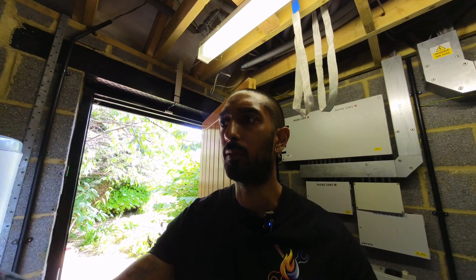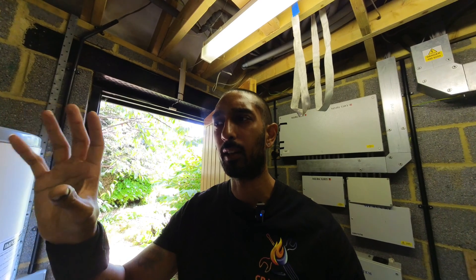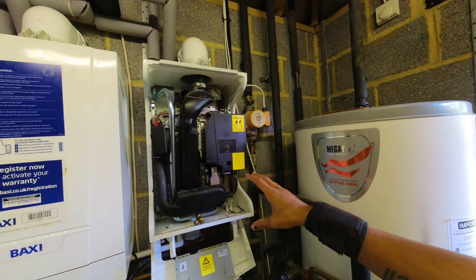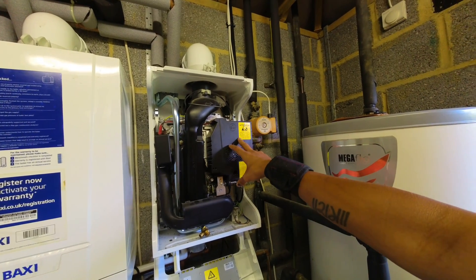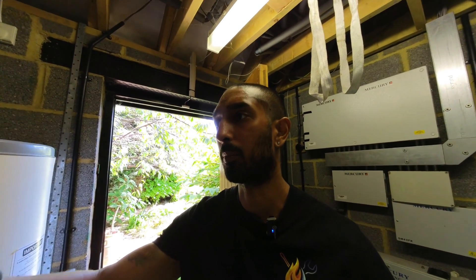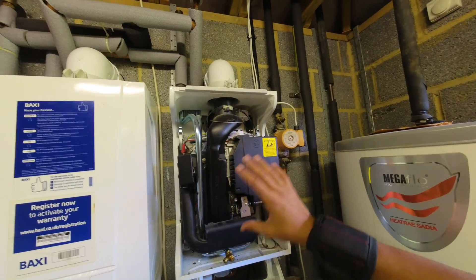When I was working in social housing I found that a lot of these used to fail. I was told by Baxi it was something to do with being fitted on S-plan systems — the voltages coming back from the three-port valve would fry the PCBs. You'd get four red flashes indicating a fan fault, meaning you had to change the whole combustion control unit. The downside is that if the gas valve, fan, or PCB fails, you have to buy the whole unit — and they're not cheap.